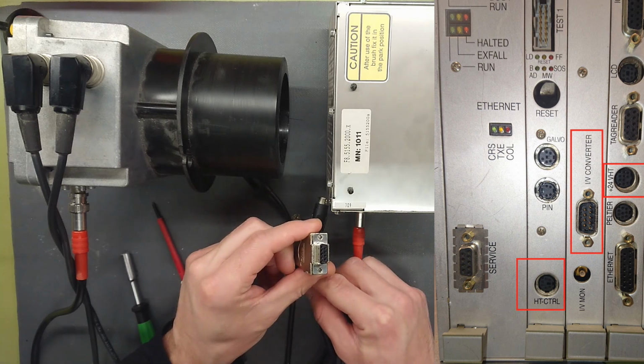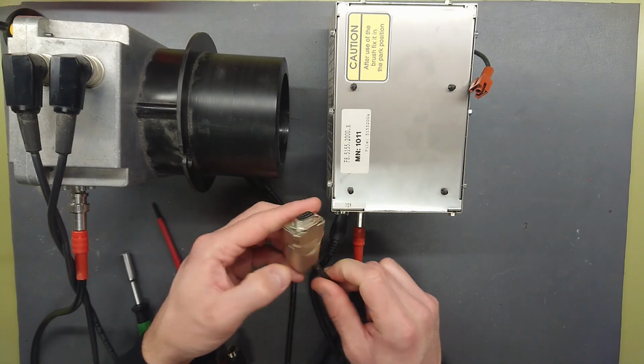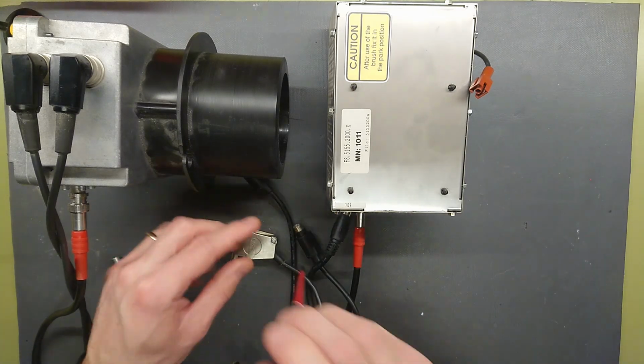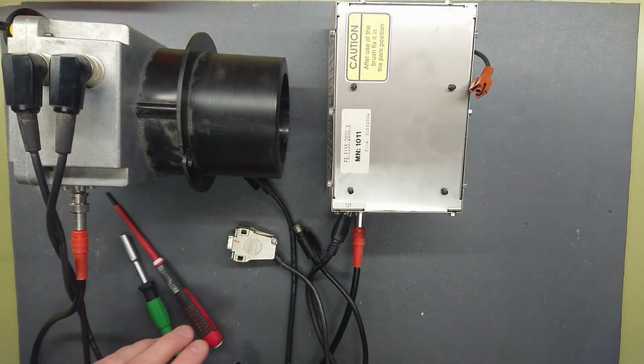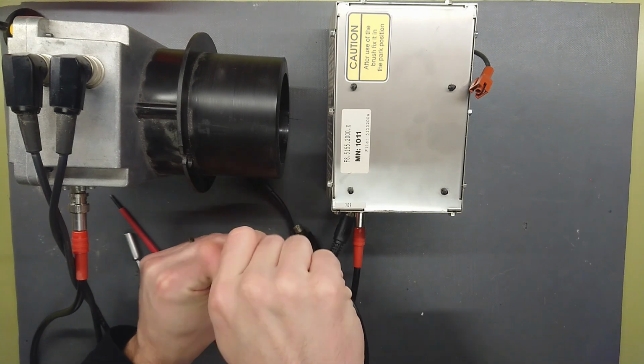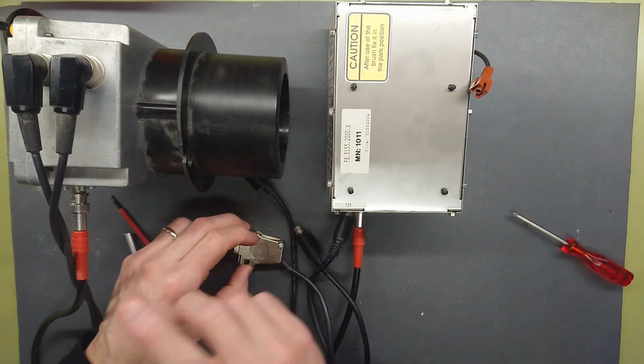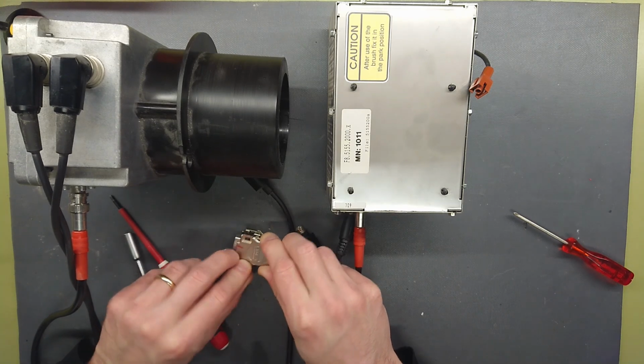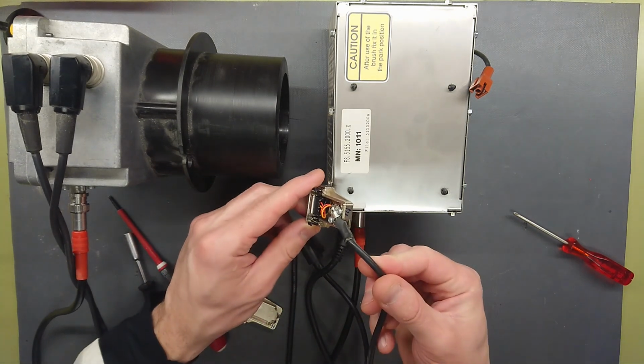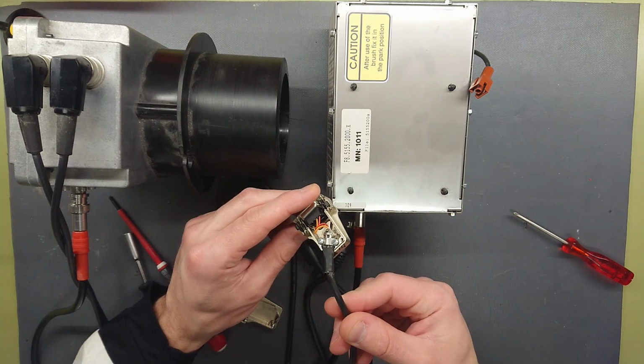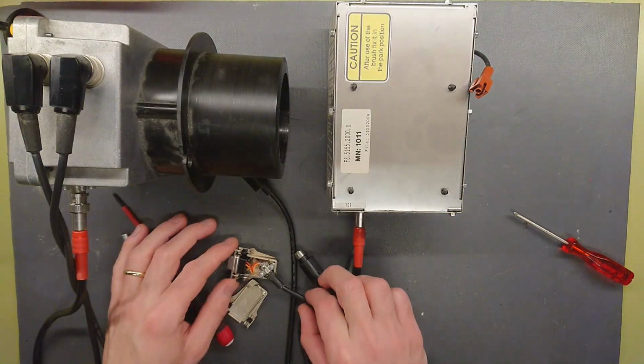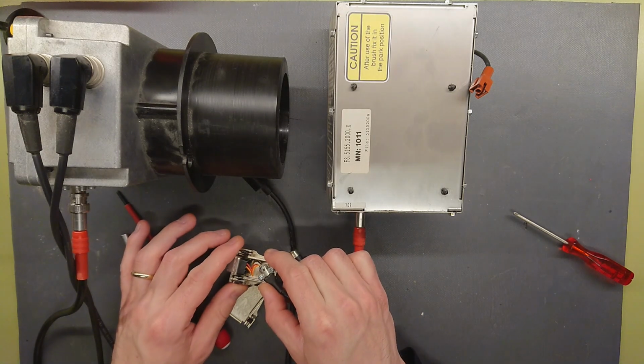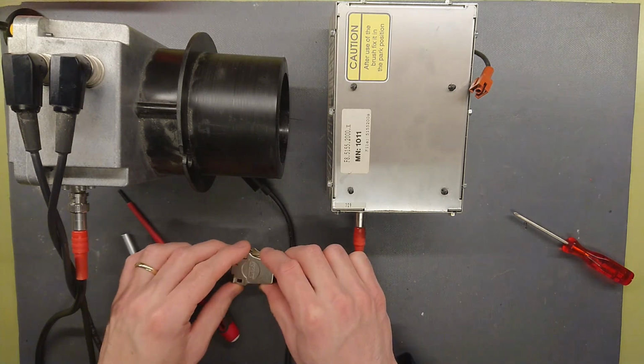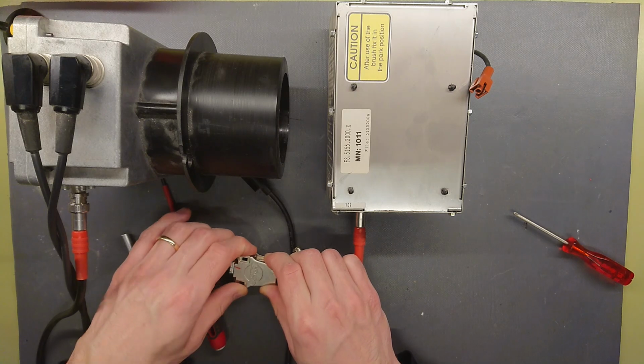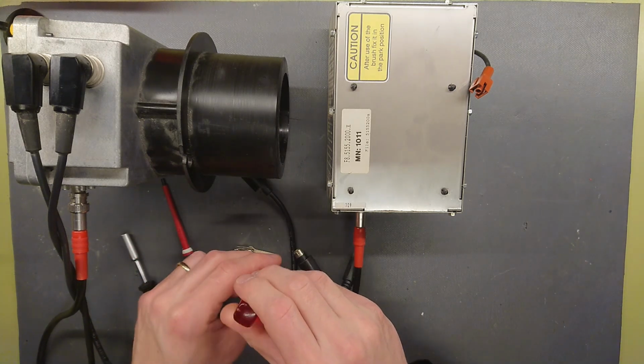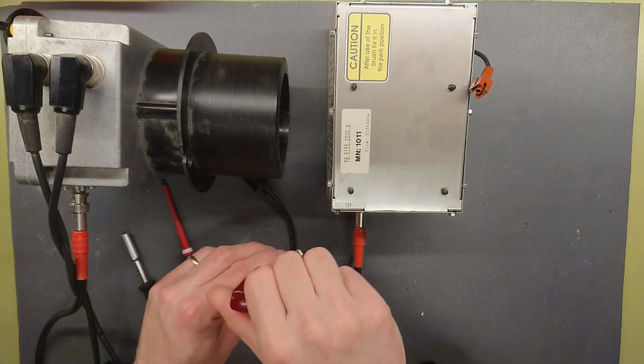And I'm not quite sure if this is just a TTL level signal or 3.3 volts, or if it's even just a regular serial output. But we will see once we get inside this box here. So we can just take a peek inside here and see that it's connected to 4, 5, 6, 7. So that does not seem to actually be a regular serial connection, that would sit on 2 and 3. So we can safely assume that this is not an RS-232 signal coming out of the PMT.